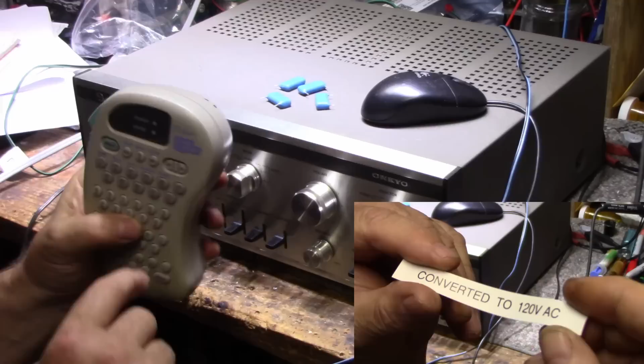The owner was also questioning me about the safety of this. As you can see, it doesn't consume any more current, it's still at 1.7 amps at full power, and there's no need to change the fuse because we're still using the same 3 amp fuse. As far as safety goes, there's really nothing to go wrong with this circuit, it's just a matter of adding another transformer in series with the other one and making sure the connections are all insulated properly and tucked away.